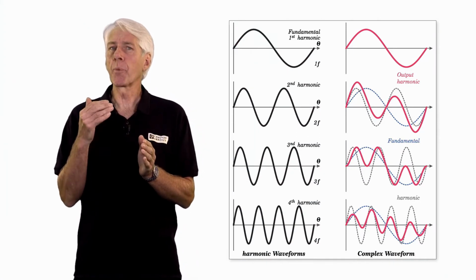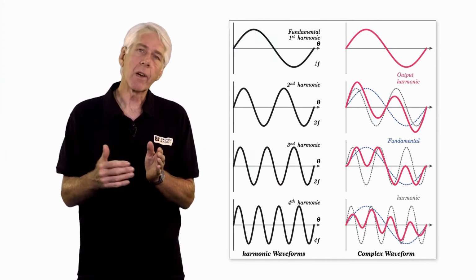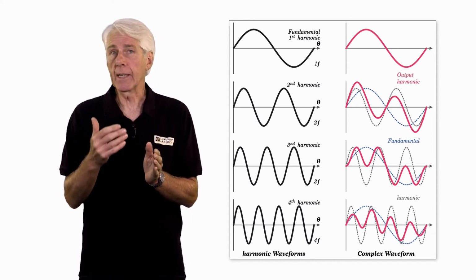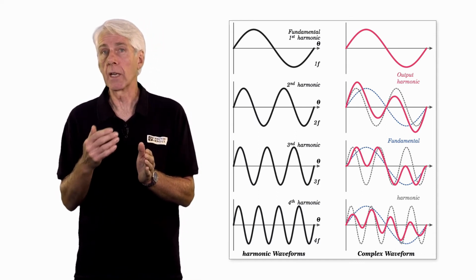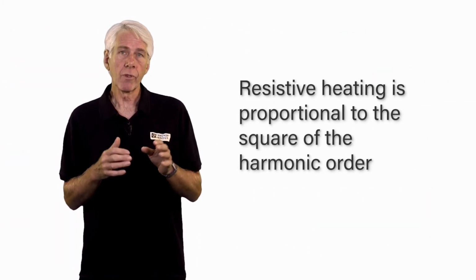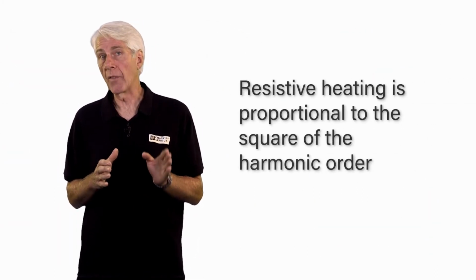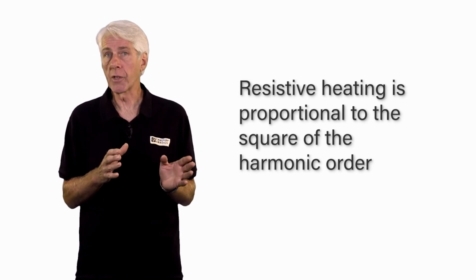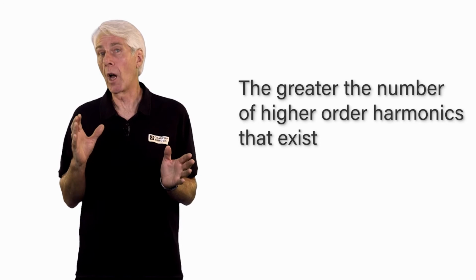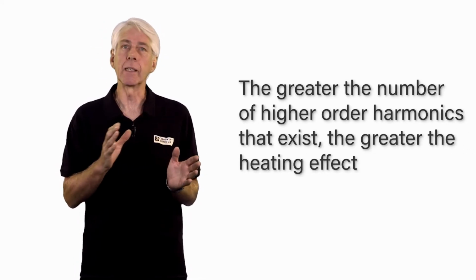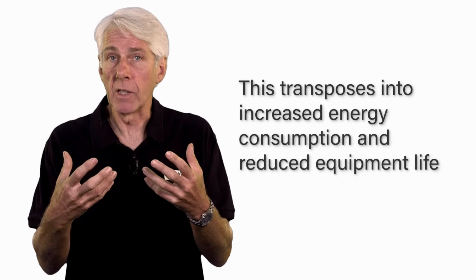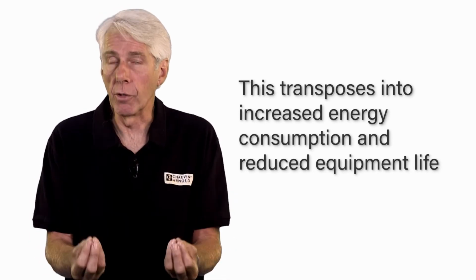Harmonics create all sorts of problems in an installation, but with regards to energy efficiency will, at the least, create increased internal energy losses in connected equipment. Resistive heating is proportional to the square of the harmonic order, so it also follows that the greater the number of higher order harmonics that exist, the greater the heating effect. And this transposes into increased energy consumption and reduced equipment life. Now, as with all the energy efficiency issues discussed so far, the effects of harmonics can be mitigated in various ways, but you need to measure them first.